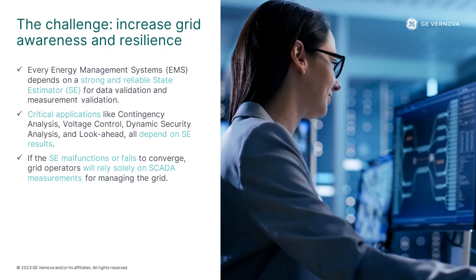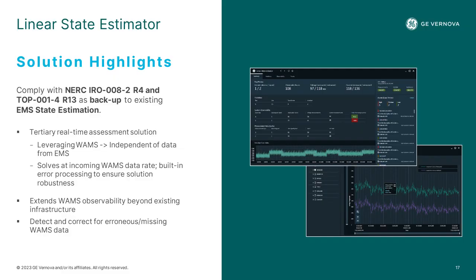Now, we know that state estimation is one of the fundamental applications in the EMS. We use the results of the state estimator for advanced applications like contingency analysis, dynamic stability analysis, and look ahead analysis. So ensuring that we have a stable and reliable state estimation solution is important. And that's where our linear state estimator comes in. It gives us end-to-end backup capability to the traditional state estimator. In fact, here in the US, there are regulatory requirements to have a backup to your EMS state estimation, and many of our customers are using WAMS and linear state estimation to meet that specific requirement.